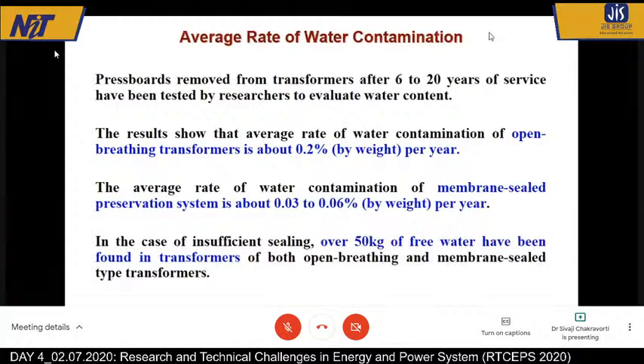An open breathing system, again for my participants, I want to say that the transformer has a breathing system. We have the conservators, breathers. Open breathing means that the oil in the conservator tank at the top is in touch with air through the breather, of course. In an open breathing system, it has been found that moisture can come in in spite of you giving silica gel and everything, whatever you have learned in your life. It will be around 0.2% by weight per year. So that means in 5 years, that 1% by weight, that much of moisture can come in. But that is if people have taken good care.